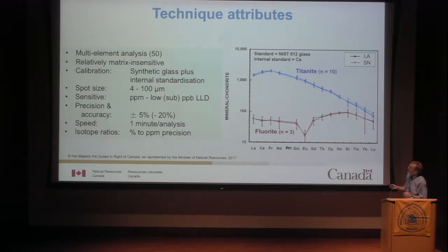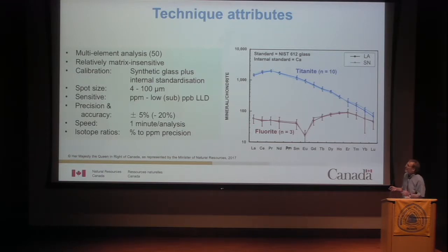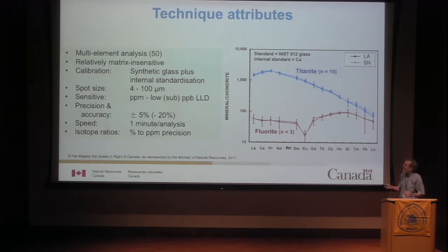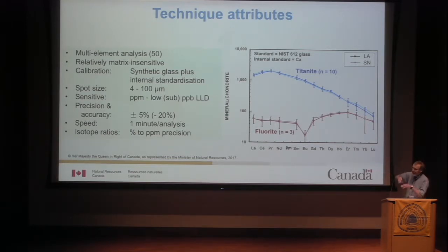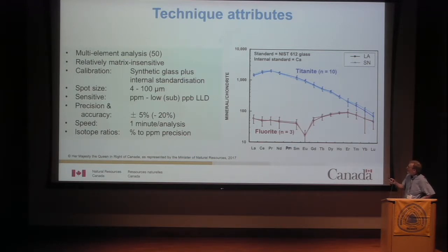Unlike the ion microprobe, laser ablation ICP-MS is relatively matrix insensitive, which means we can calibrate it usually just with a synthetic glass, then employ an internal standard to correct for the amount of material actually ablated relative to the standard — the internal standard being an element in the sample whose concentration we already know, typically a major element.